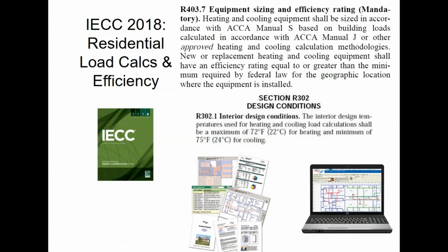As part of the Energy Conservation Code, load calculations are a code requirement. You have to do ACCA Manual J load calculations. Or if you have another load calc method, you have to have your local authority having jurisdiction, so your local inspector, approve your method. Or just go ahead and use Manual J like everybody else does. So you have to use ACCA Manual J to calculate your loads, and you have to use ACCA Manual S.